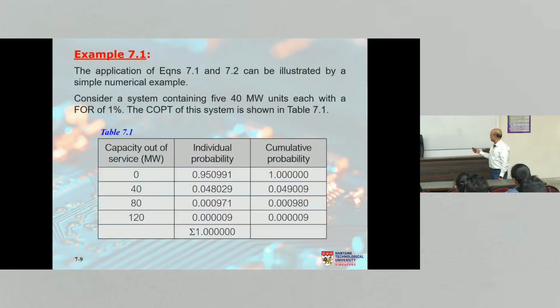Okay. So let's look at an example. Nothing better to understand than by use of an example. The application of equation 7.1 and 7.2 can be illustrated using this example. Five 40 megawatt units, each with a forced outage rate of 1%. So you can use the binomial distribution to calculate the capacity outage probability table, right? So that's what I have done.